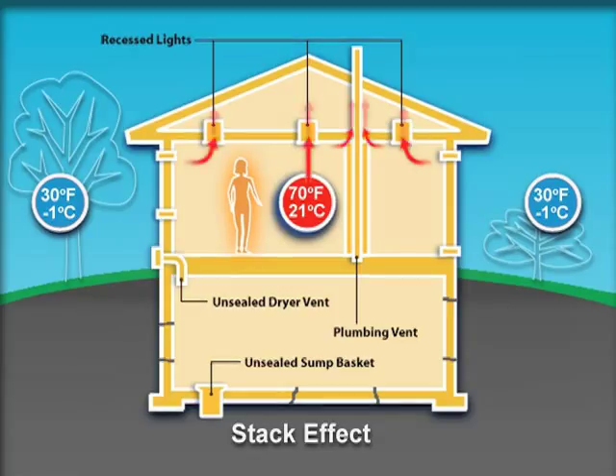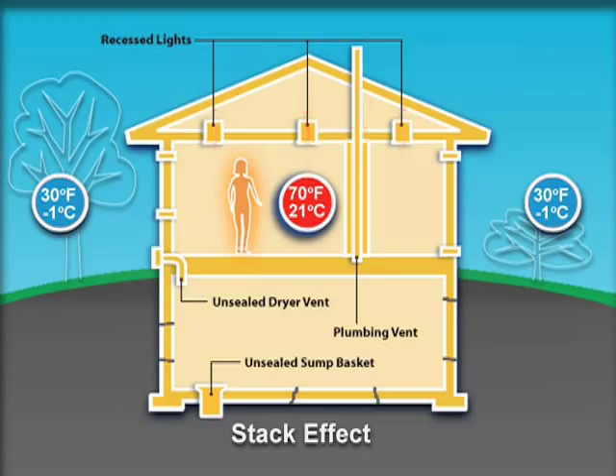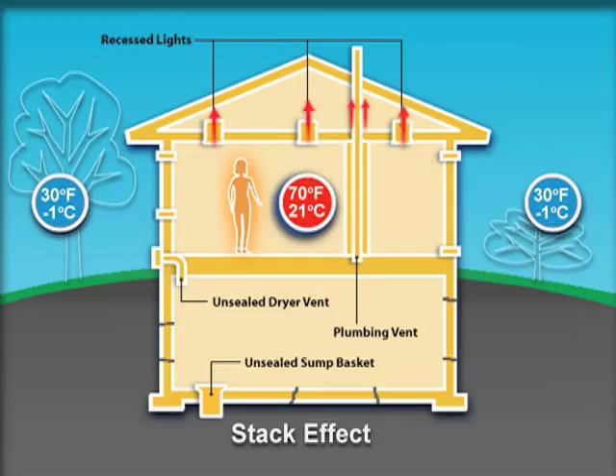When the temperature is warmer inside than outside, a flow is created through penetrations in the top of the building. This warmer air flows through recessed lights, fireplaces, and flues. This is called the stack effect. As this warmer air leaves the building, it must be replaced with cooler air from the outside, resulting in uncomfortable drafts.